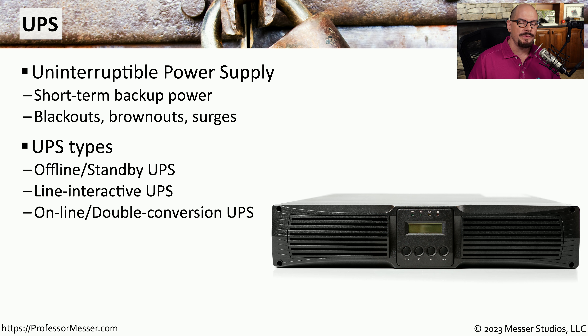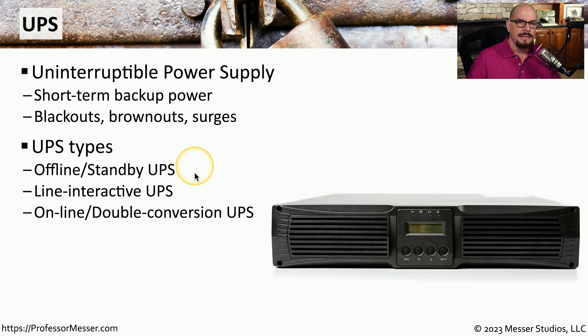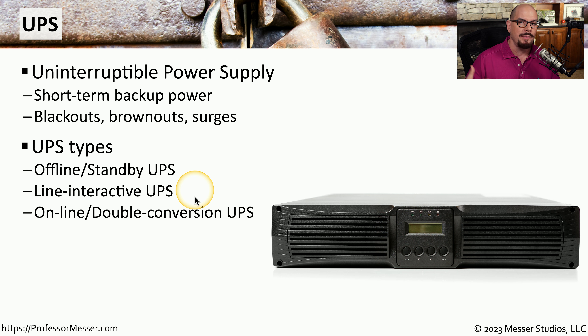A UPS commonly has batteries or some other power source inside that allows us to keep up and running even when the main power is no longer operational. It can get us through blackouts, brownouts — a drop in voltage — or surges, an excessive amount of voltage. There are different types of UPSs depending on your requirements and budget. Lower-end UPSs tend to be offline or standby UPSs, which run on main power but switch to battery backup when main power fails. A line-interactive UPS can slowly increase voltage if you see a drop on your main power line, which is especially helpful in areas prone to brownouts.